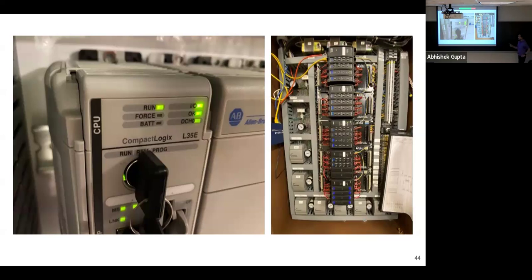There's a key switch here, and it's in the remote position, REM, which means it can accept commands from a remote connection. If it was in the run position, you would not be able to write to it, even if you had access. This is something we would call out in an assessment — it should always be in the run position unless it's in program mode locally. If it's in remote, that's a risk.